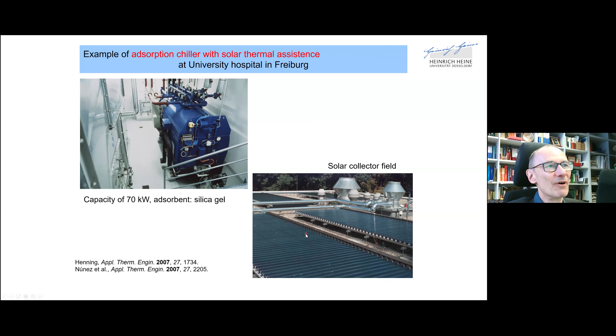Actually, you can use this technology not only for generating cold, but also for dehumidification. If humid air is drawn through the porous material, it adsorbs water, and dry air exits the cylinder on the other side. For regeneration, this cylinder turns constantly, and through one quadrant of the cycle, hot or warm air is blown through, with both air streams fully separated. The warm air drives out the water from the porous material to regenerate the active sorbent.